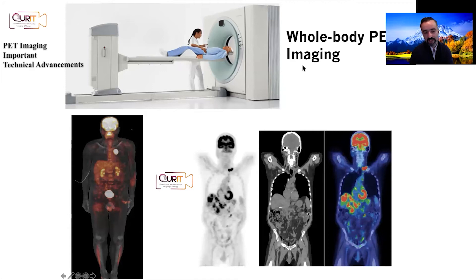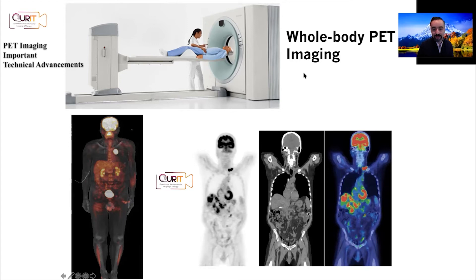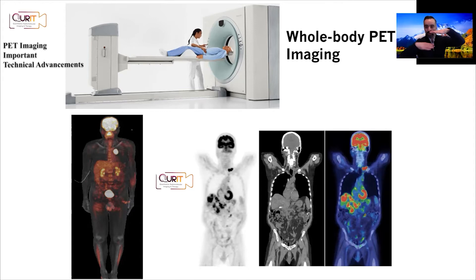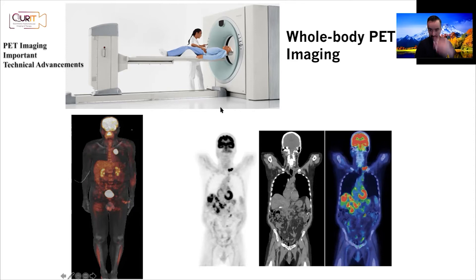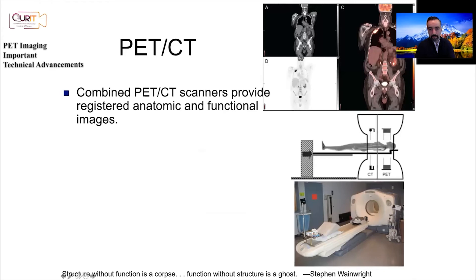PET imaging is now very common in clinical oncology in a whole-body sense. A typical axial field of view is 15 to 25 centimeters, which cannot cover the whole body in one acquisition. Therefore, multiple bed positions — typically six to eight beds — are used, either in a step-and-shoot mode or with continuous bed movement, to achieve a whole-body image.